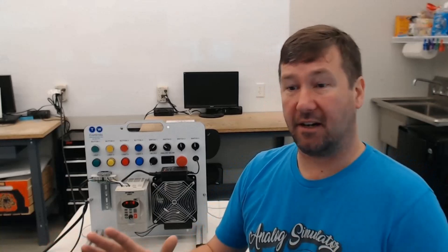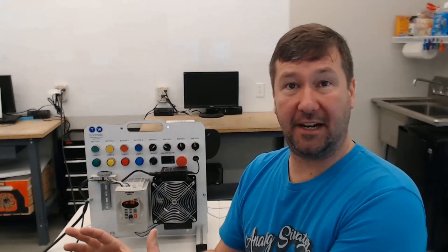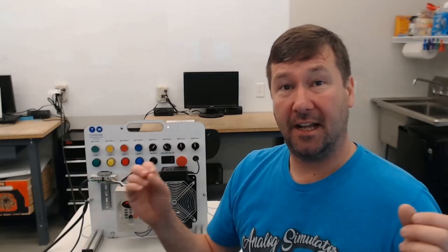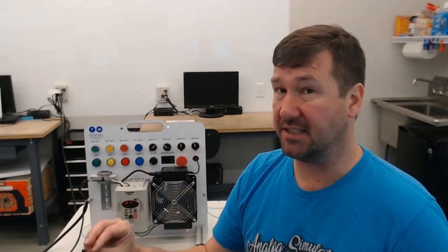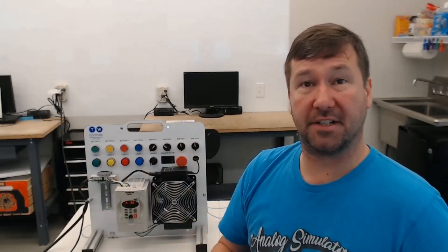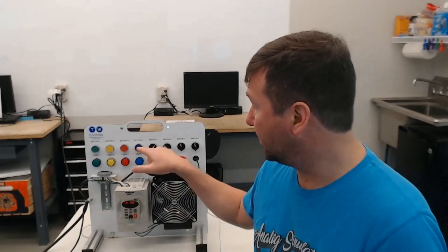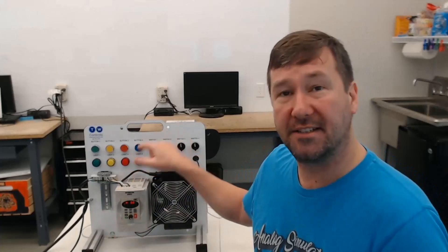So what do I see when I go out into a plant? They'll have a machine that runs great. And they'll tell you, man, this thing runs great, but never turn the power off to it because you can't get it started back up. And you go in there and all of a sudden you'll see where they have this abandoned code in there. It never says anywhere in it that the program is called. It's just if an OTE is present. So if there's an OTE, whether it's being called or not, it is going to write a zero to that data table box.